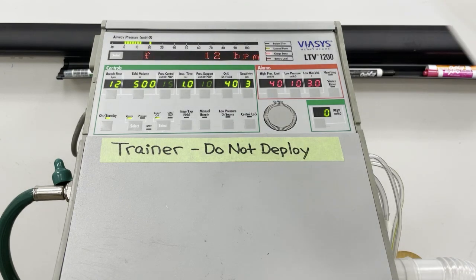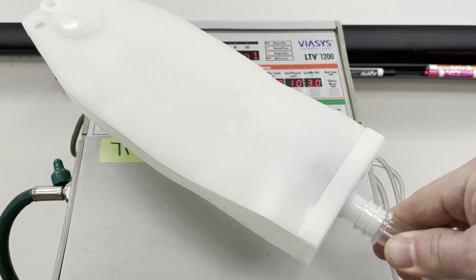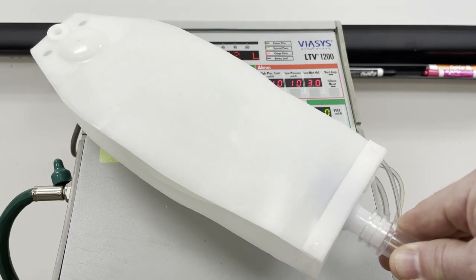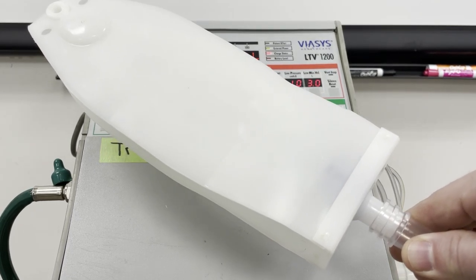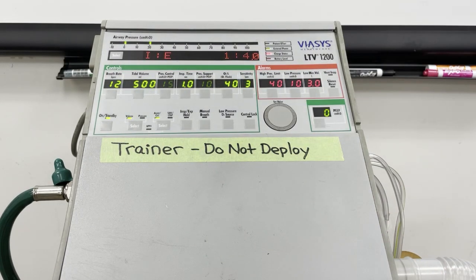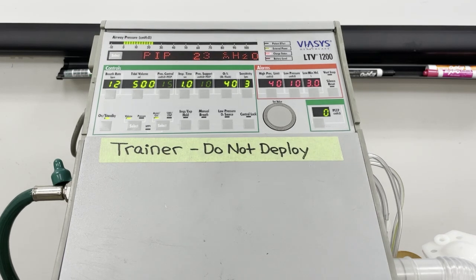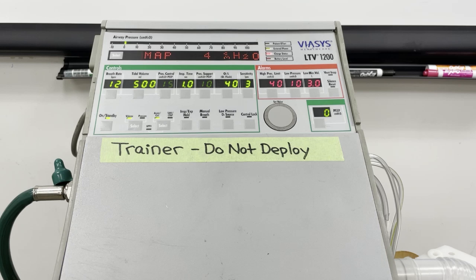In the video here, I've attached a lung simulator to the vent circuit. You will not have a lung simulator when you are at the patient's bedside. Why is that relevant? Well, if the vent begins to cycle and there's no patient connected to the other end, the low pressure alarm will start to go off. This is going to complicate the setup.